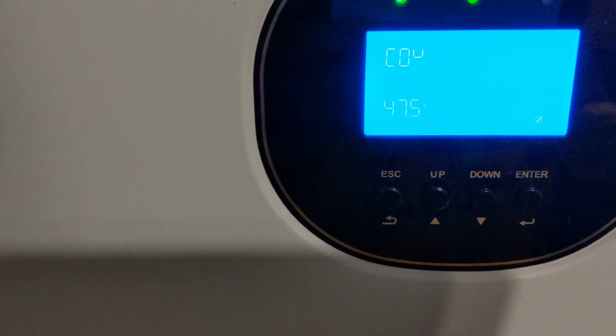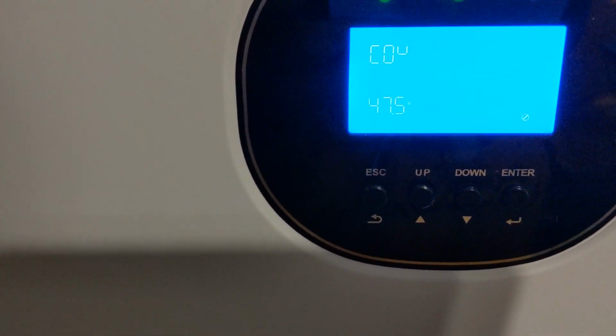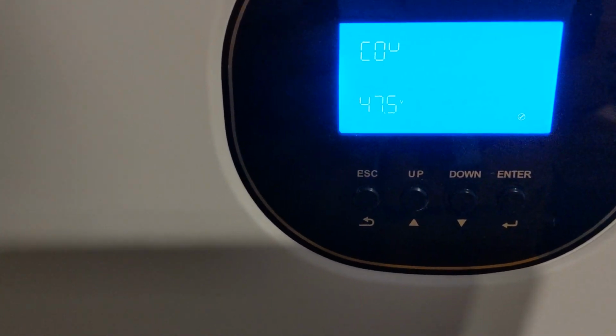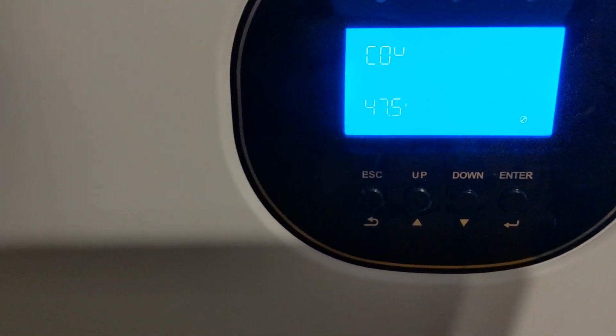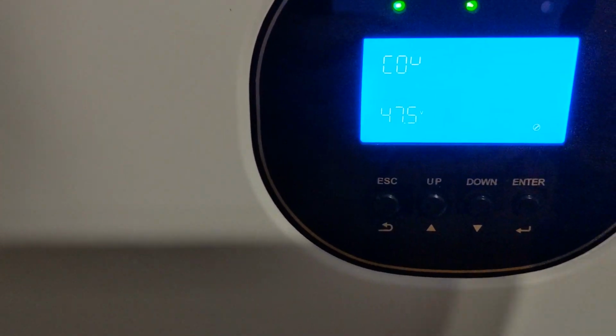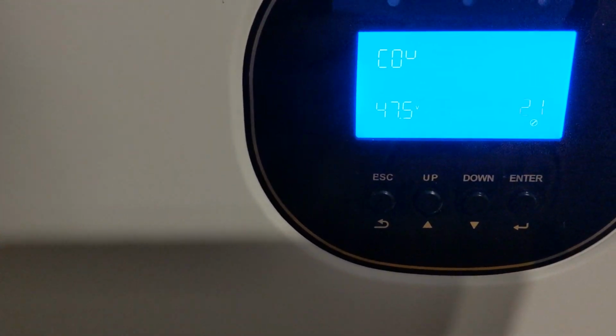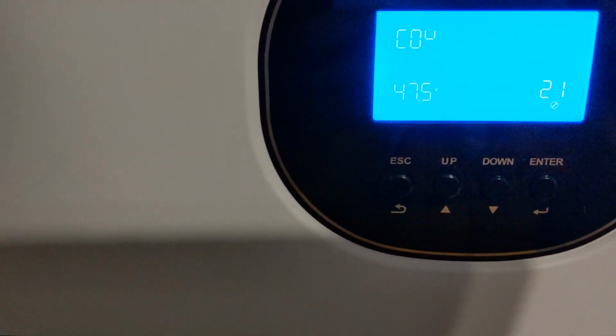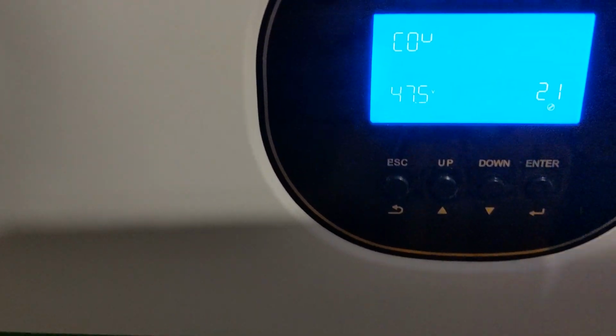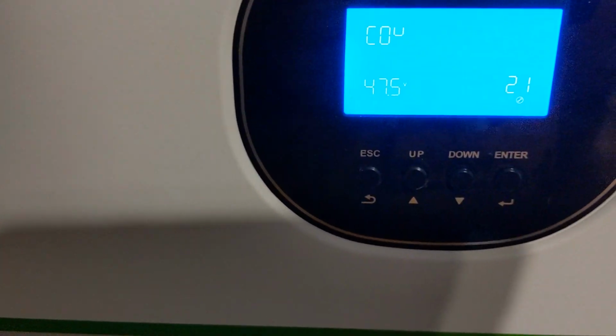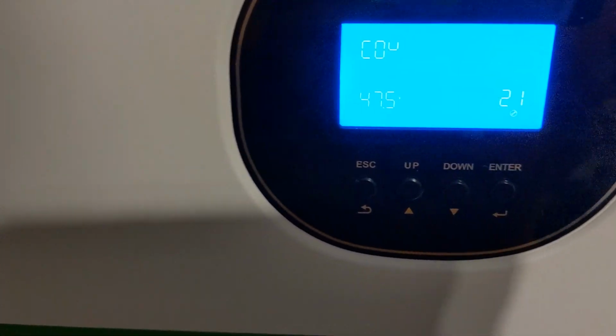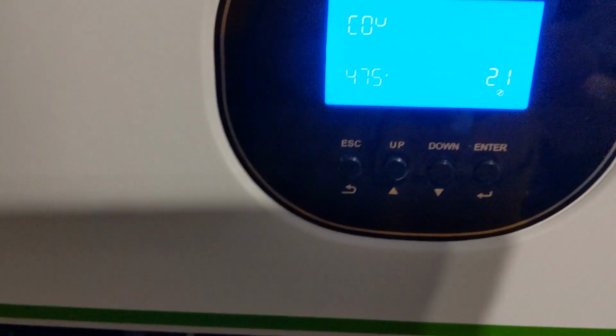If you're using some sort of custom batteries where it says set this as your low voltage cutoff, you could choose that as well. This is set in here. My battery BMS has its settings as well, so between the two of them, this should cut off before my BMS cuts off, and that should prevent the BMS from ever having to shut the batteries off from the unit. So you definitely want this higher than whatever your BMS set point is.